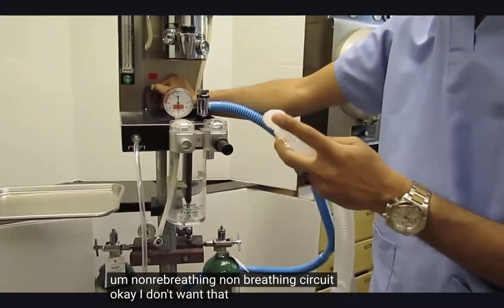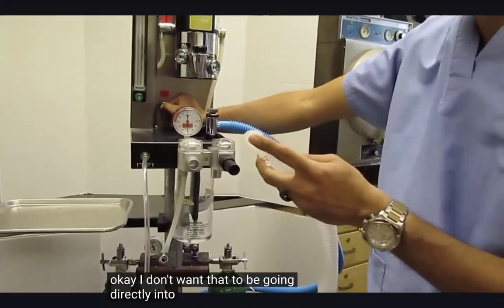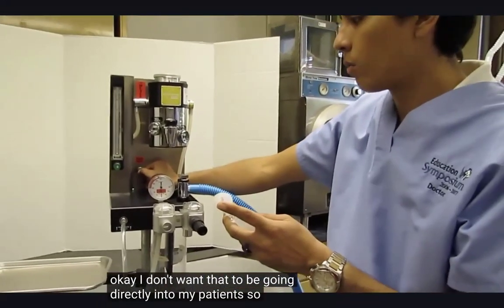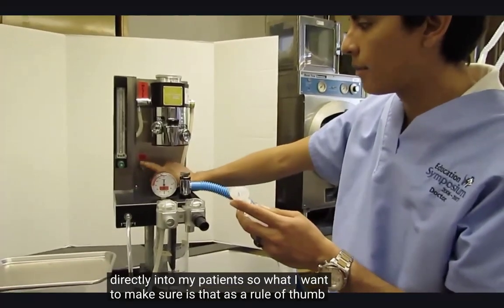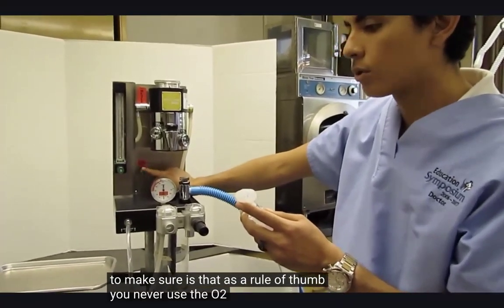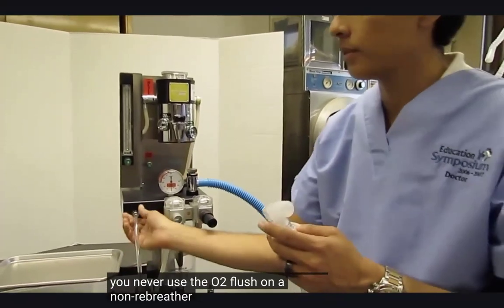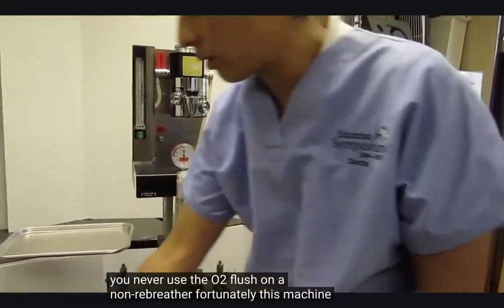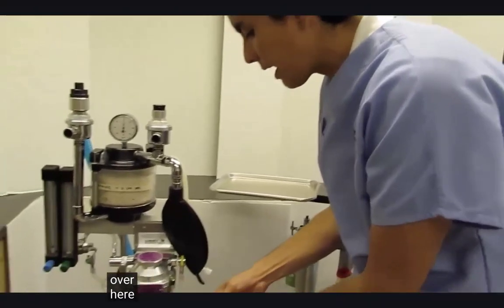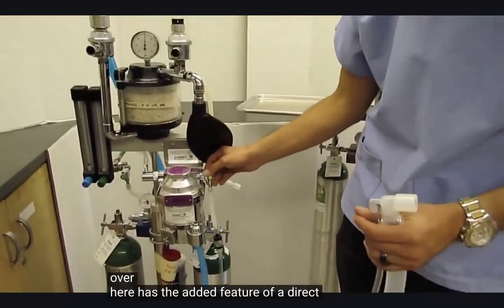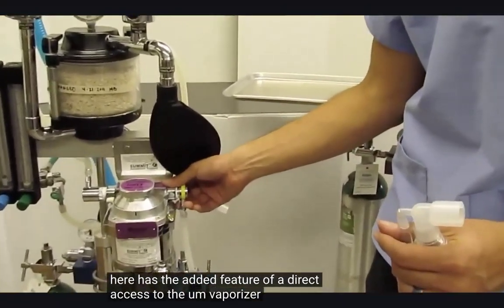I don't want that to be going directly into my patients. So as a rule of thumb, you never use the O2 flush on a non-rebreather. Fortunately, this machine over here has the added feature of a direct access to the vaporizer outlet.